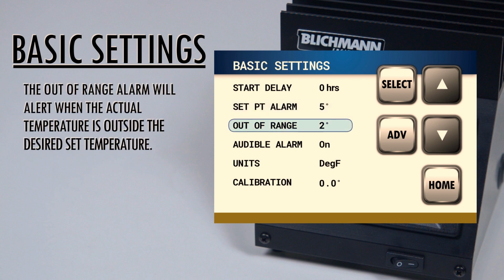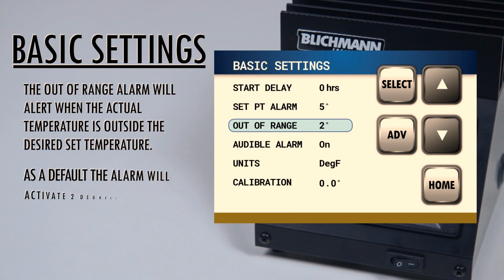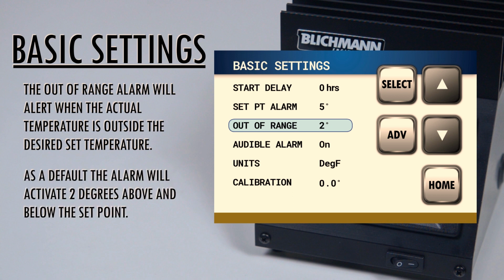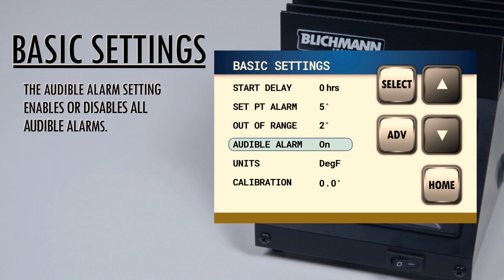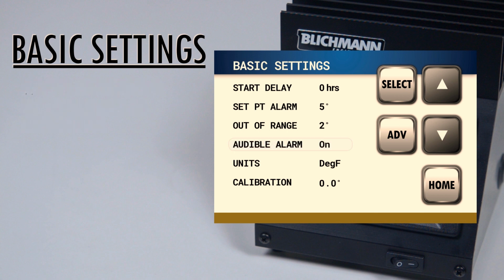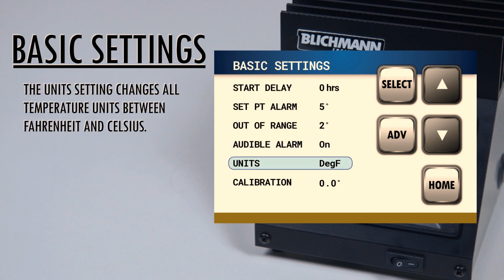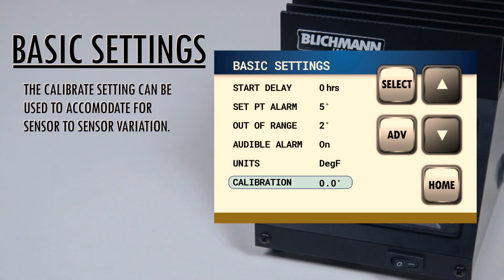The out of range alarm will alert the user that the actual temperature is outside of the desired set temperature range. As default, the alarm will activate 2 degrees above and below the set point. The audible alarm setting is used to enable or disable all audible alarms. The units setting changes all temperature units between Fahrenheit and Celsius. The calibrate setting can be used to accommodate for sensor-to-sensor variation.